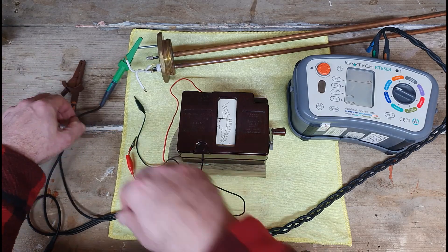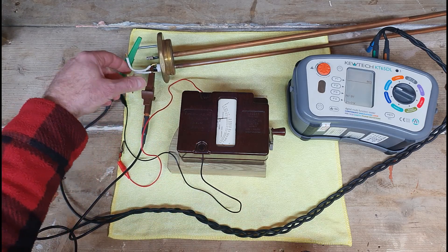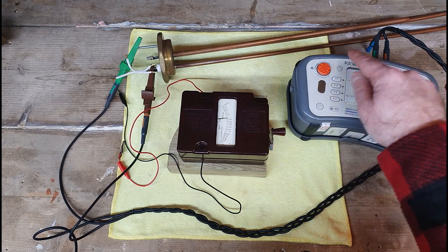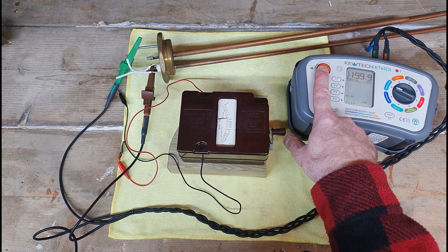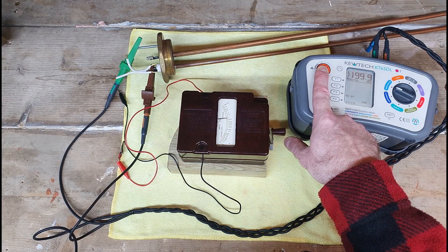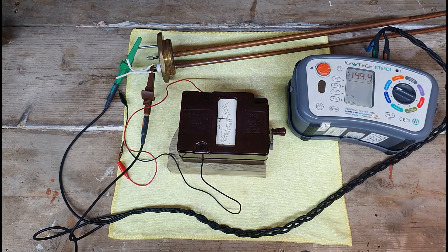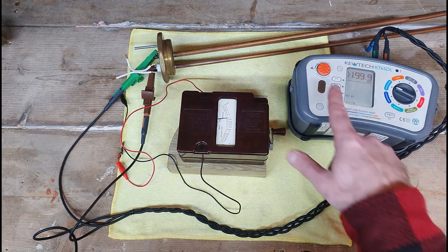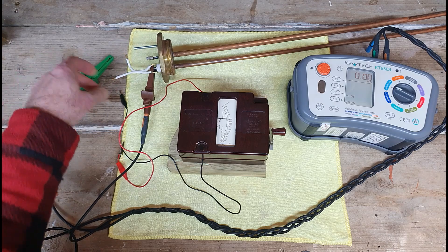Undo these croc clips from the series three, keep these out the way over here. We'll just basically confirm our readings. Connect up there, don't need to deal with any of this stuff. Can you see the screen there? Yes, we can. Let's press the test button there and yeah, it's version of infinity, above 199.9. So that's perfect there. We can even test it this way just to prove dead short, and yeah so we've proved that one's working fine.